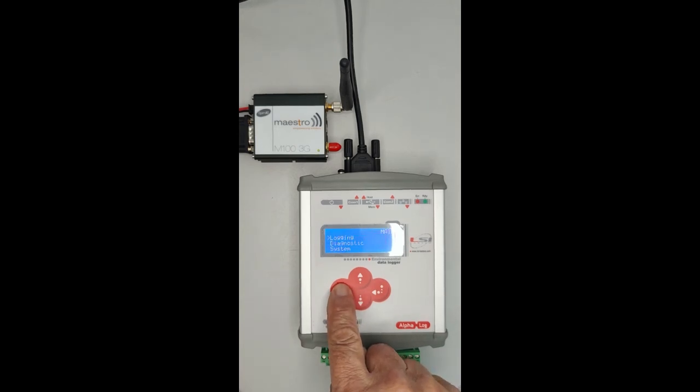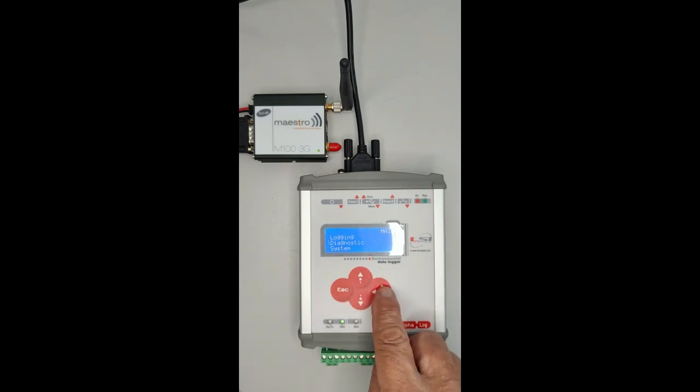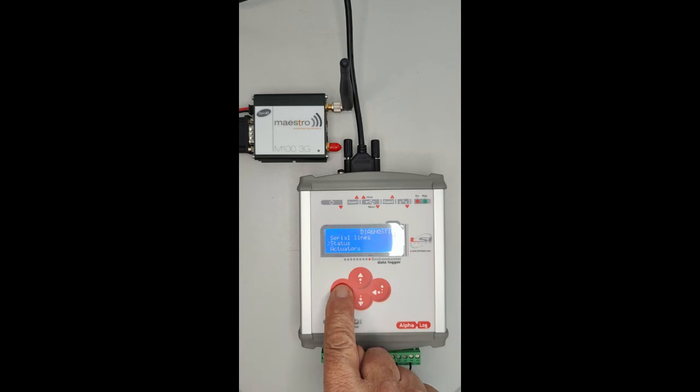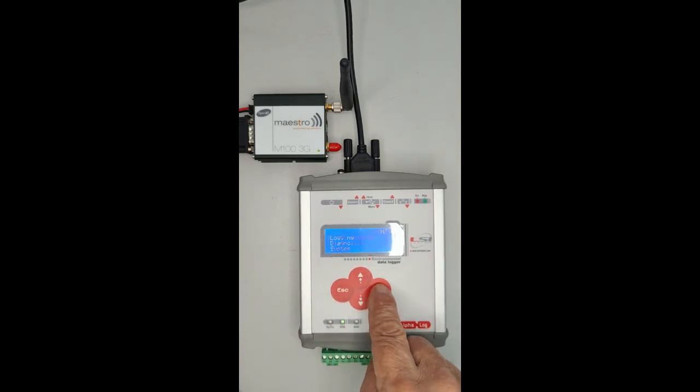First, we need to check the power supply level. Press escape until you reach the main menu. Go down up to Diagnostic and press Enter. Go to Status and press Enter. The status must run as normal. If the appearing information shows run limited or low battery, you need to check the power supply level, it must be greater than 12 volt.